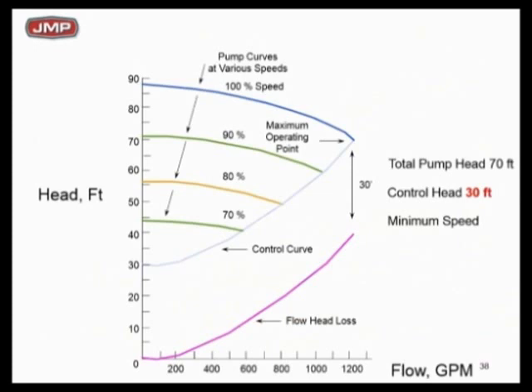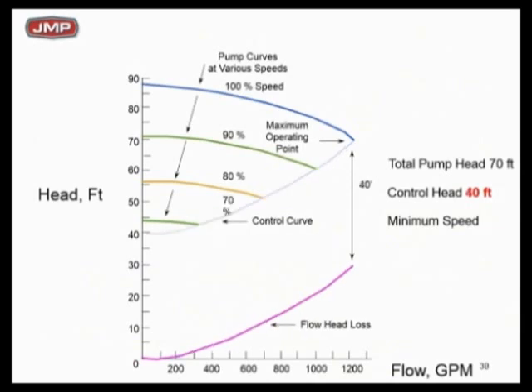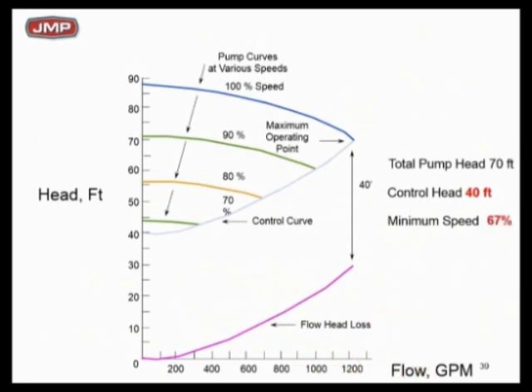At zero flow, what is the minimum pump speed? At zero flow, I've got to maintain 30 feet — not zero. With 100% variable head I'd go to zero head at zero flow, but here I've got to have 30 feet. So roughly 60% pump speed is the minimum speed of this pump at zero flow to maintain that 30 feet for the critical zone. That's where people are getting in trouble. Now if I increase the control head to 40 feet — you see the blue line shifting up — my minimum speed is now 67%. The control head controls the minimum speed of the pump.